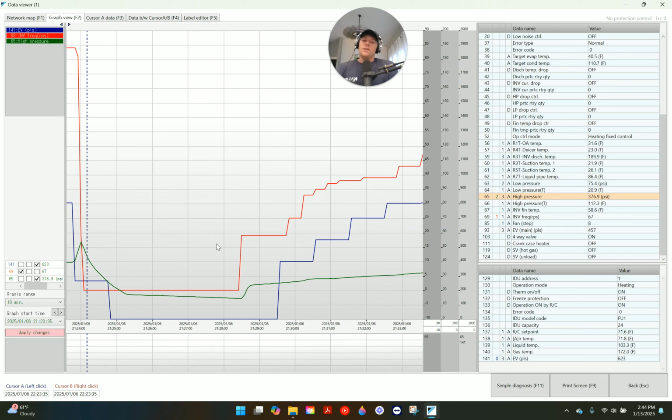Again, this is going off of superheat or subcool or operational data, as opposed to actually measuring the liquid line length and going through the installation manual to find out what those charges are. And now I've even found in those installation manuals that the specific charge amounts have even been off in certain applications, right? This all comes down to airflow. This comes down to application, system selection, load sizing, occupancy, ambient conditions. All of those things play a factor in how the charge affects the system and the system's operation.